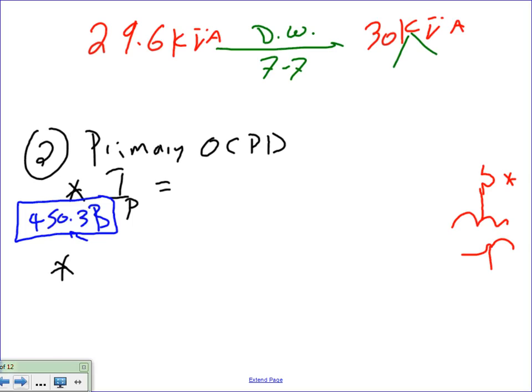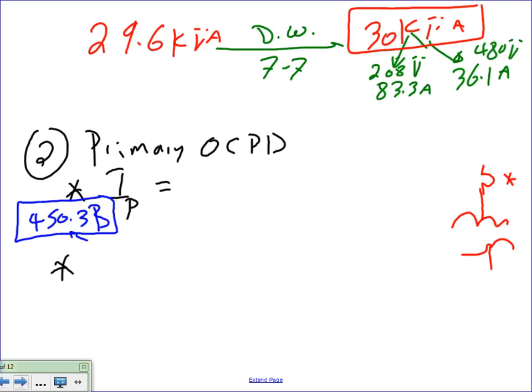So from here, I'm just going to say the 208 volt side was 83.3 amps, and for the 480 side, directly from this table, the 480 was 36.1 amps. How did they come up with this? You took the kVA divided by the voltage times 1.73. It's not rocket science. But from this size, you can find all this stuff directly. So my actual size is 30 kVA. Any question, guys, about the 30 kVA size that we have?